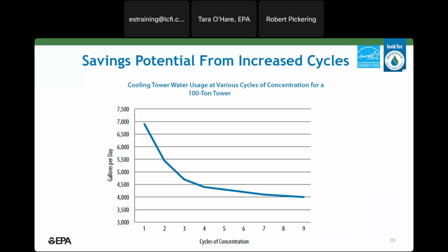And this chart here shows the water consumption of a theoretical 100-ton tower at various cycles of concentration. You can see by the shape that as you get higher cycles, there's a flattening of the curve, since a greater portion of the water is being evaporated rather than blown down. As you can see, this threshold point is around 5 or 6. So it's a good target to try to achieve 6 or greater cycles. And everything beyond that is kind of gravy.